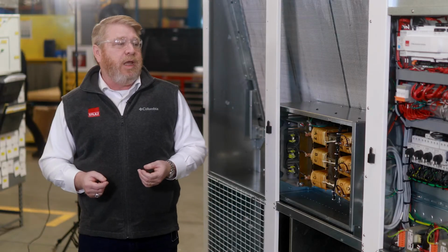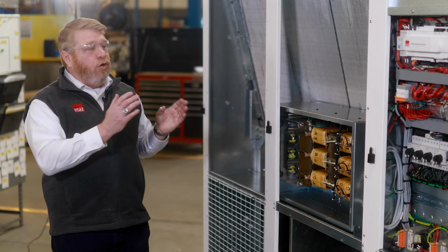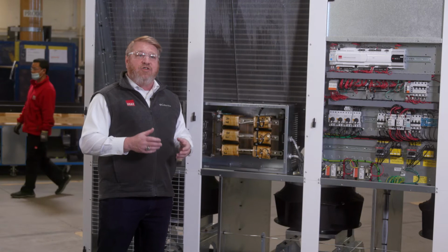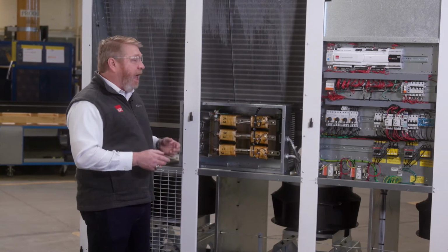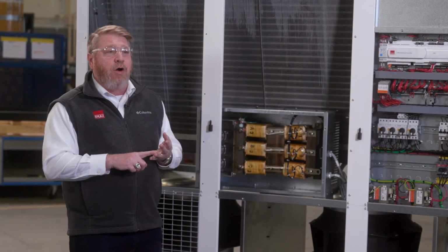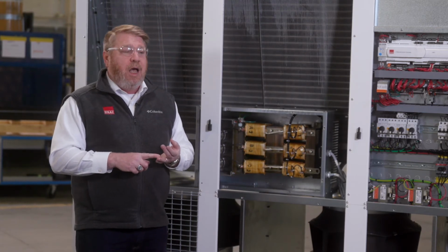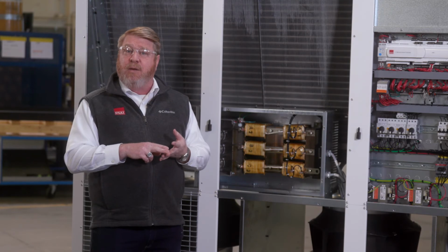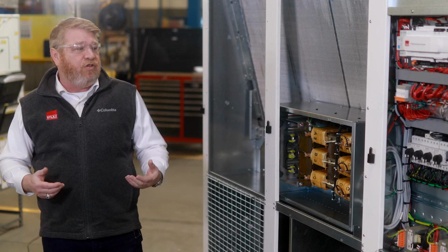And the best way to imagine total harmonic distortion is we know that the power signal coming into the device has a fairly pure sine wave. Now, as we either electronically commutate or use the VFD to change the frequency, what we see is additional information is added to that power wave at different harmonics. Now, the negative to that is if we have those additional signals being added to the sinusoidal power input, we expect to see things like increased peak current, greater temperature rises within the equipment. We can see higher electromagnetic emissions, and we can even see at higher frequencies core loss within the motor itself.